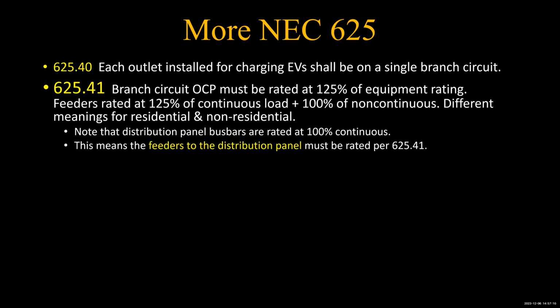Okay, so the calculation, and that's your wire sizing as well, because you're assuming it's a continuous load, even though we know charging 30 miles an hour may only be for an hour and continuous is 3 hours. But, you know, the NEC is pretty conservative, so we do that. And who knows, you may not charge continuously every night, but there may be that one night where you drove to Miami and back and you used up 120 miles. So you're going to charge for a little more than 3 hours to replace that.